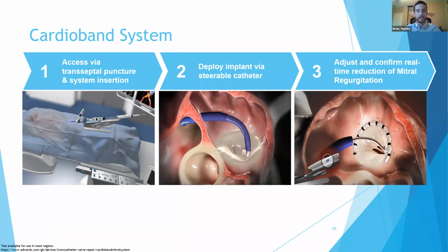So you have what you see in the picture on the left-hand side, this multi-handle delivery system with all of these catheters, and you've got these knobs and handles that you move and turn. And the whole point of that is to be able to get this ring into the proper position so that you can drop anchors in, plant it down, and pinch the annulus to be the proper size or the original size that it was. So let's take a look at first the delivery system.